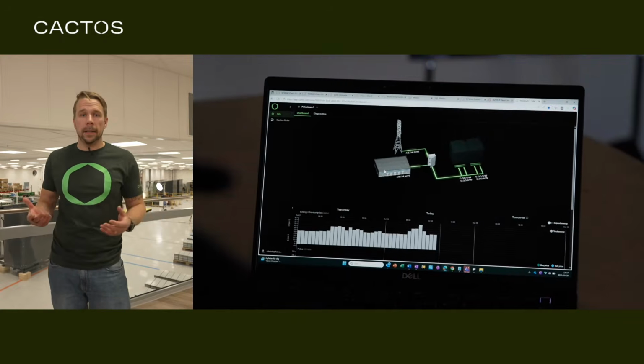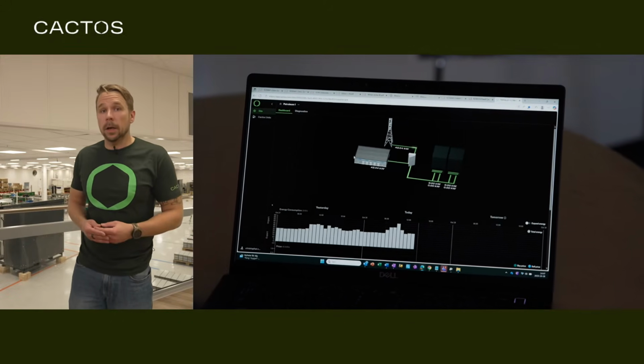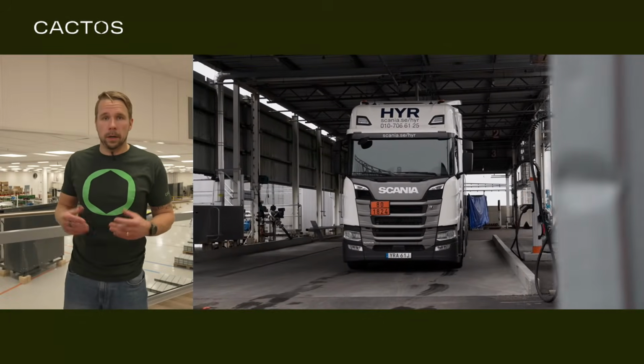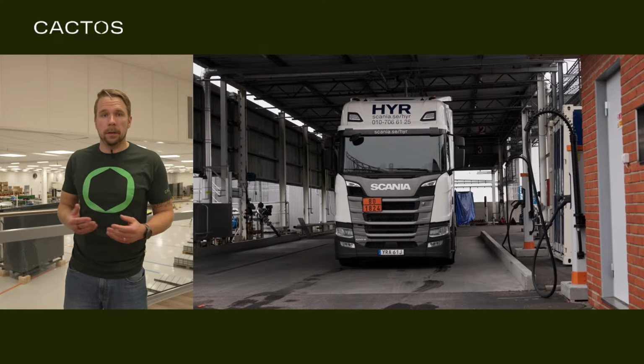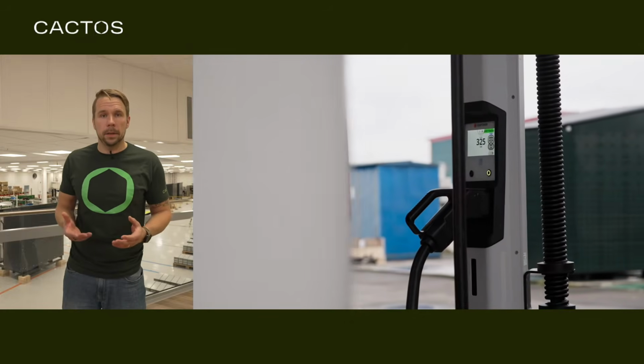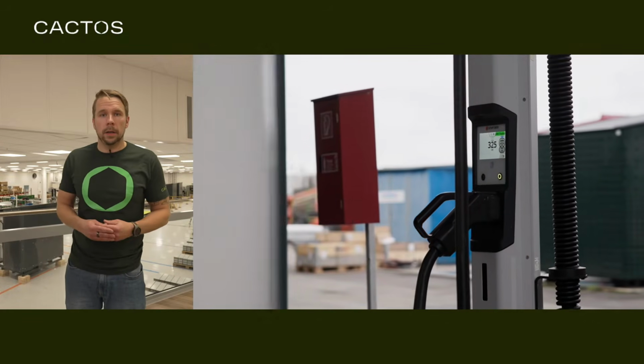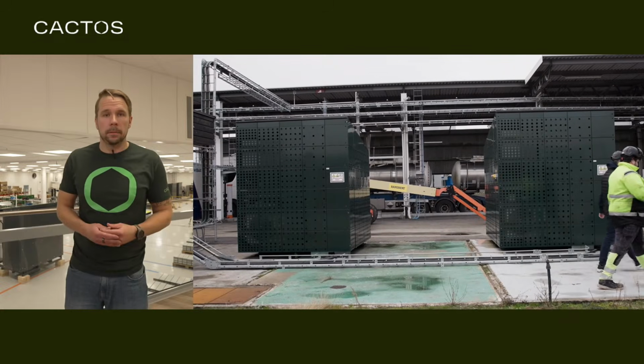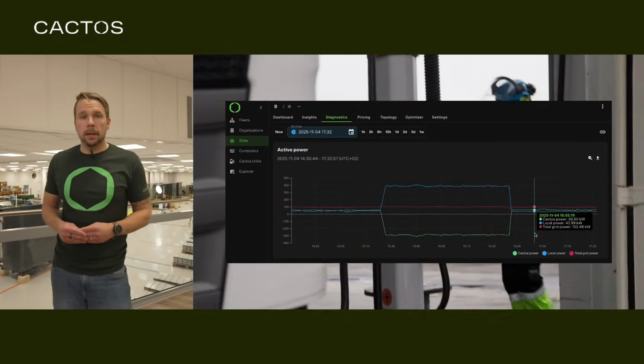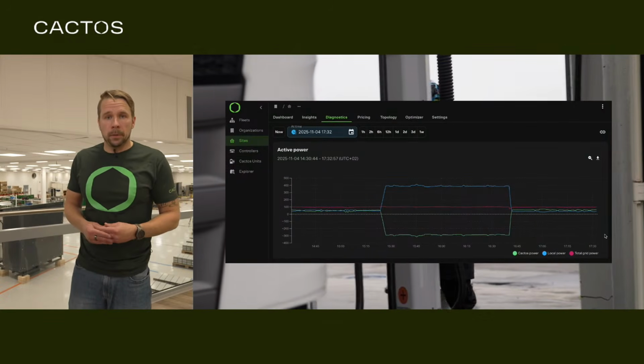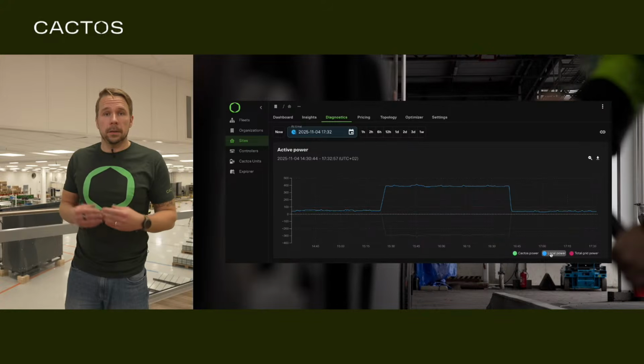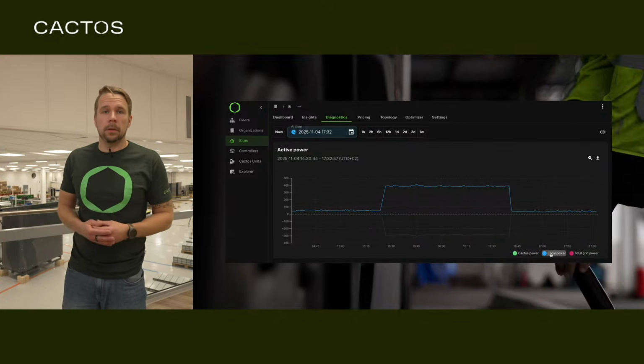We supplied them with an 860 kilowatt-hour Cactos energy storage system that does peak shaving. As shown in the graphs, when the truck charges at more than 400 kilowatts, the batteries simultaneously discharge at 300 kilowatts, leaving only 100 kilowatts to be taken from the grid. Once charging is done, the battery slowly tops up from the grid to prepare for the next charging event, enabling electric transport of chemicals.